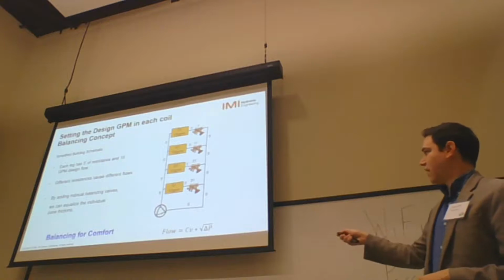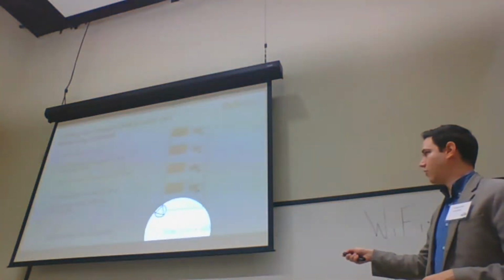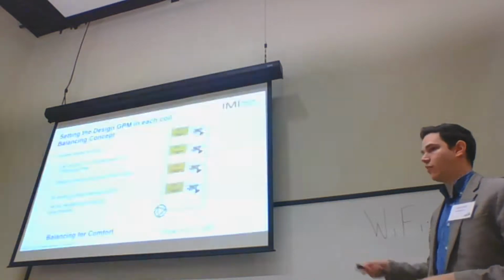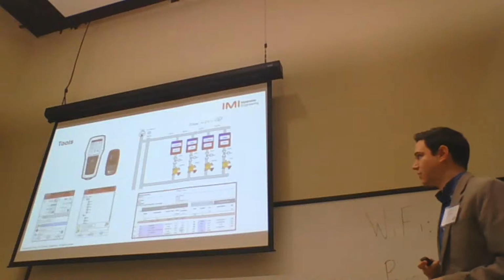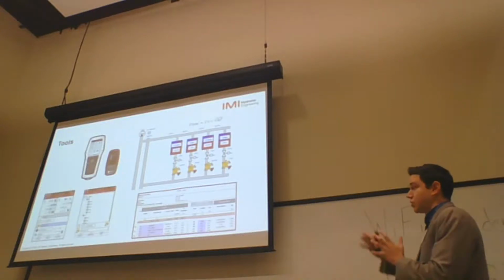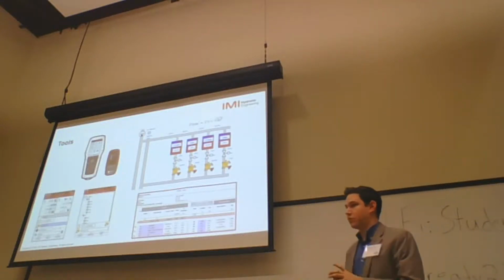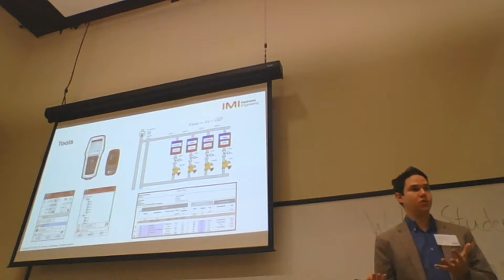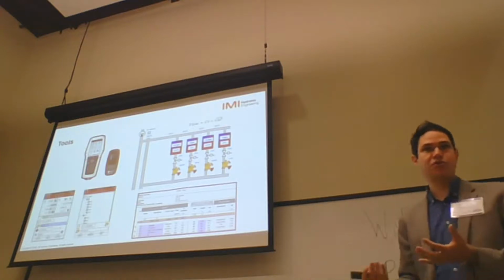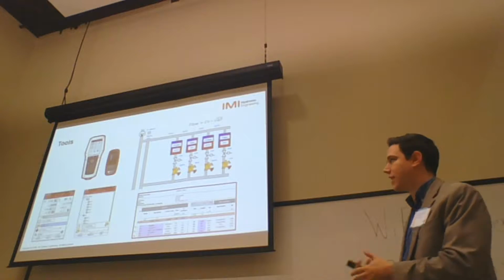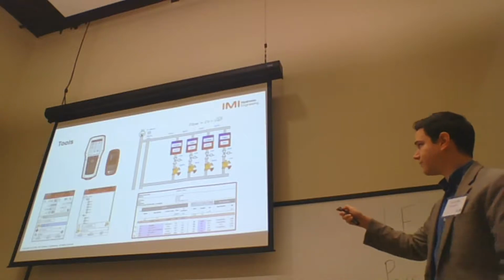And the main equation for balancing is always focusing the flow. It's equal to CV times the square root of differential pressure. That's how we always calculate it to get the right GPM. So to achieve all of that, it's important to say that there are many tools and devices that could be used to help improve and save time on the installation.